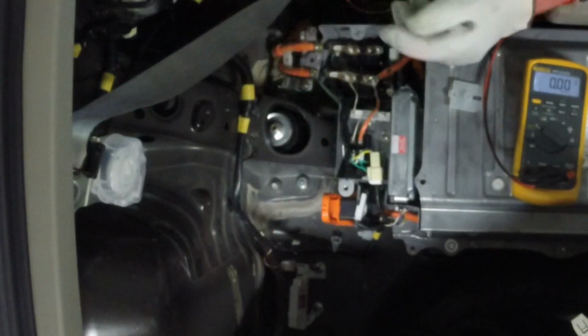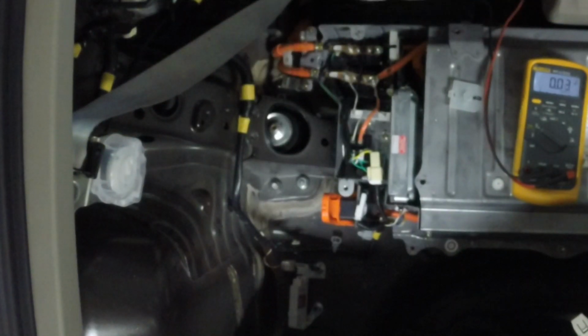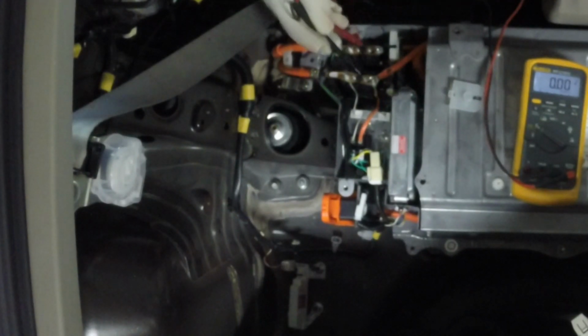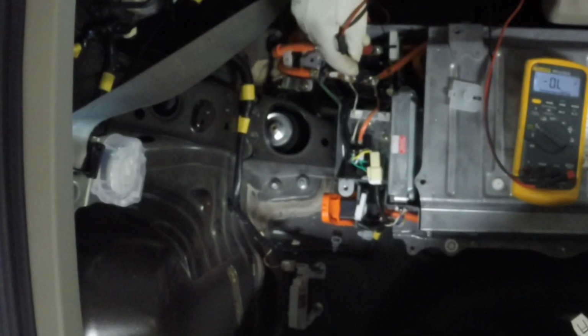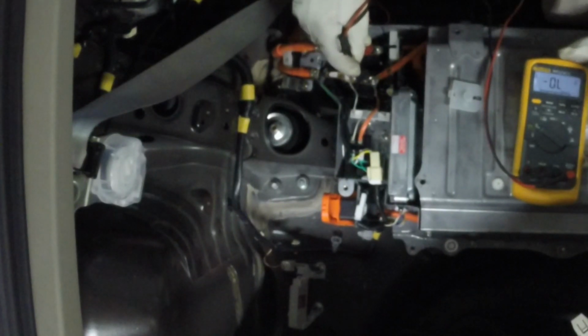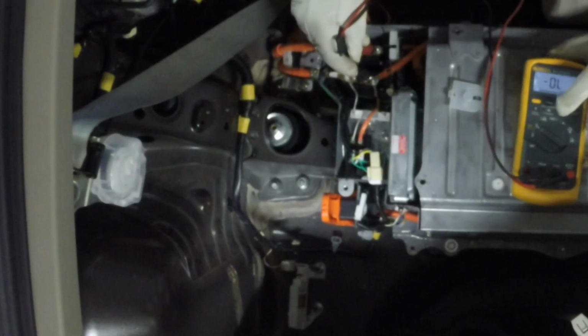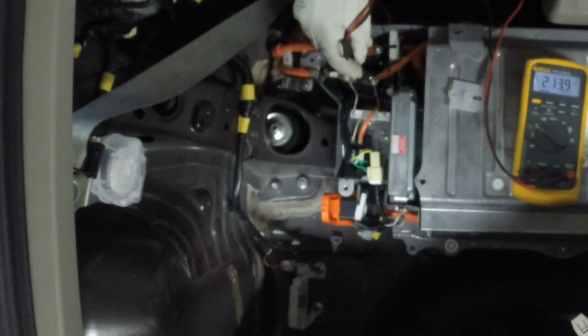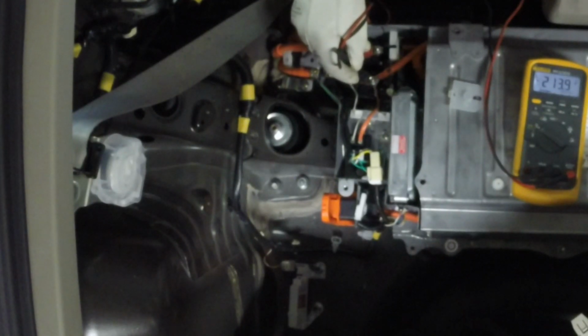Cam lock it. Now that this is plugged in, I should measure my battery voltage down here on these terminals, before what we call the contactors. Now I'm measuring OL on my meter. I'm going to go to range. And now I'm measuring 213.9 volts between those two DC terminals.